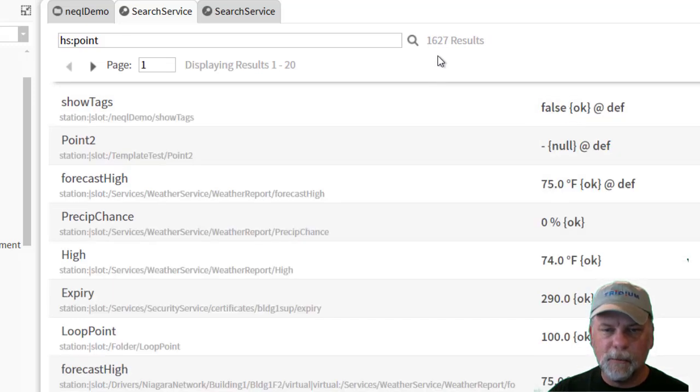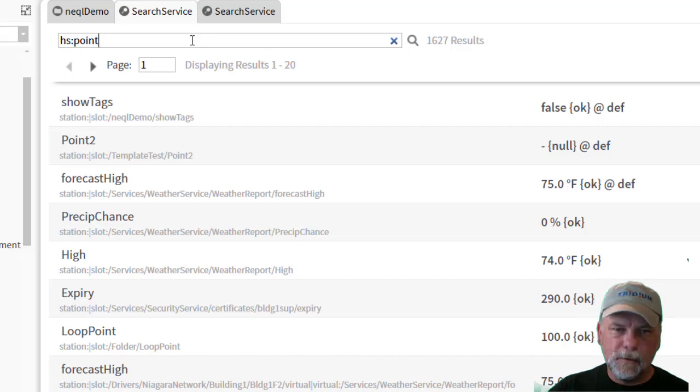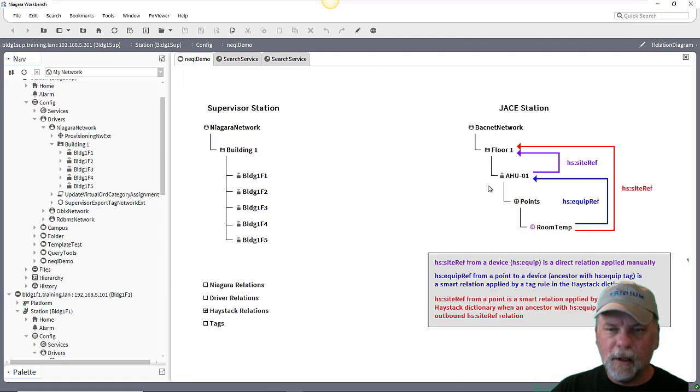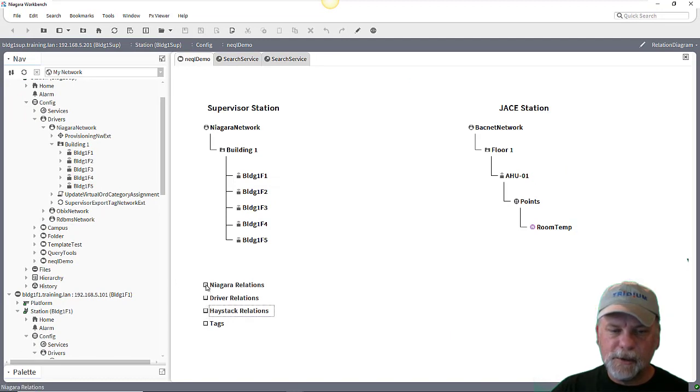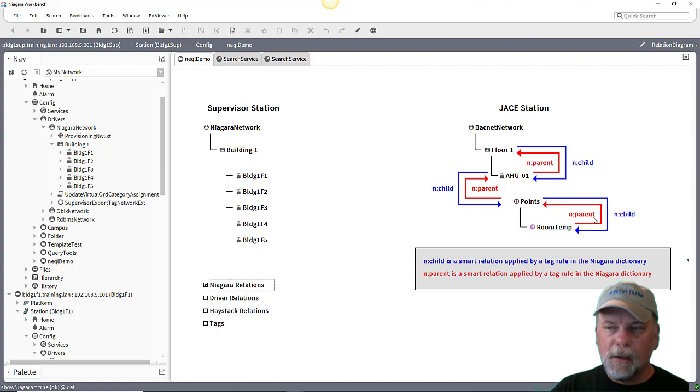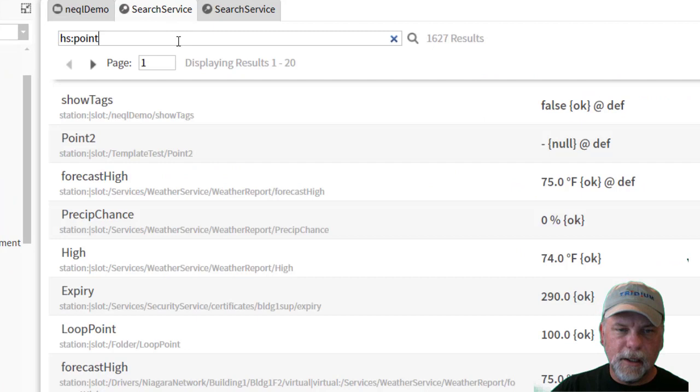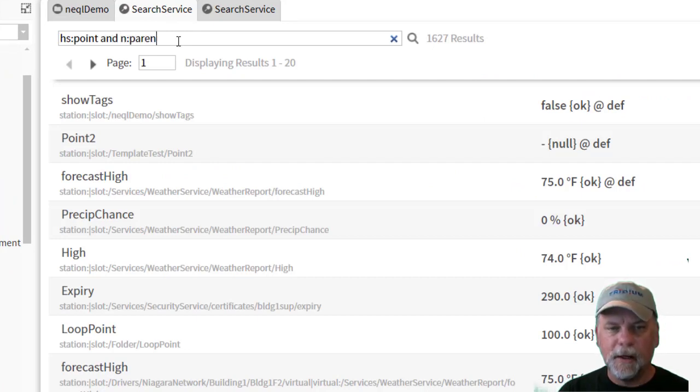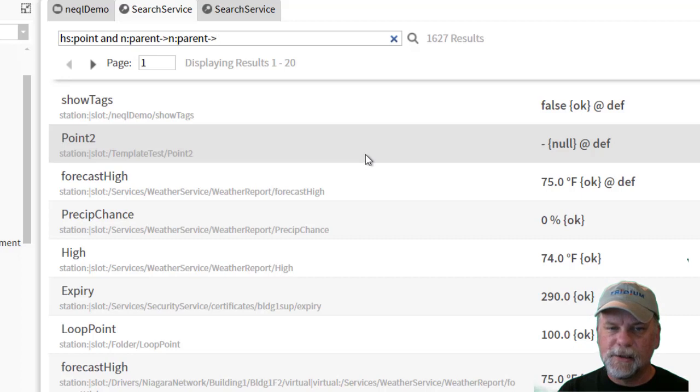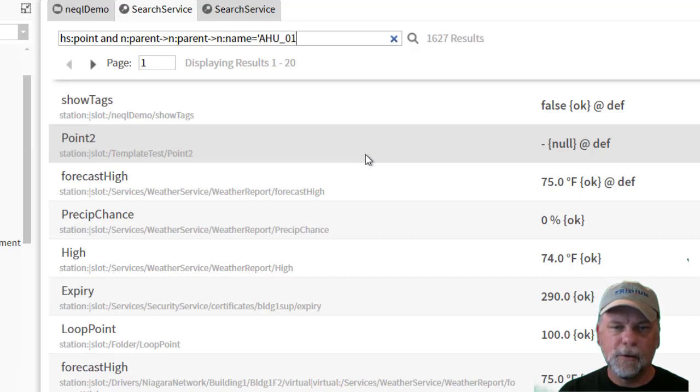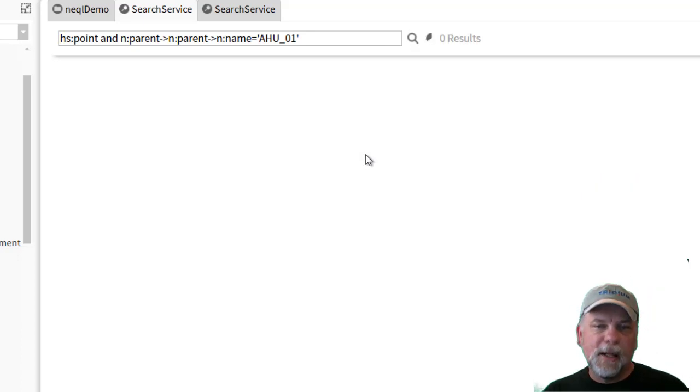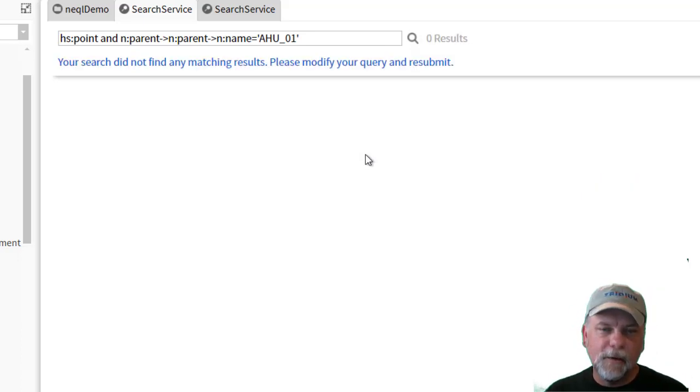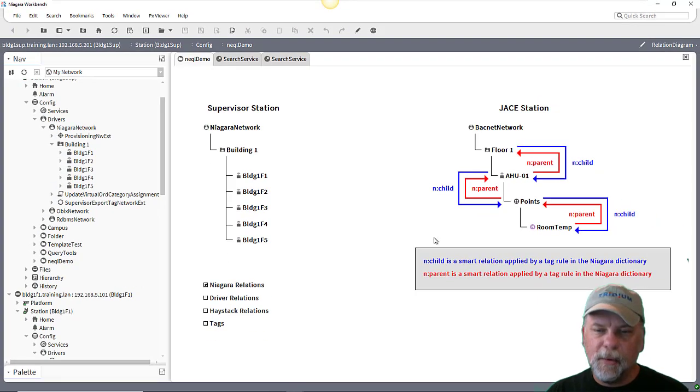And if I search for HS colon point then we should see that it'll find a good number of points here across the multiple stations. Now if I try the same type of relation traversal here using the Niagara network, I just want to show this as an example. If I use the n colon parent relation traversal it may not work for me. So if I do n colon parent outbound, that'll get to the points container, n colon parent outbound which would be the device, and then check n colon name equals AHU underscore 01.